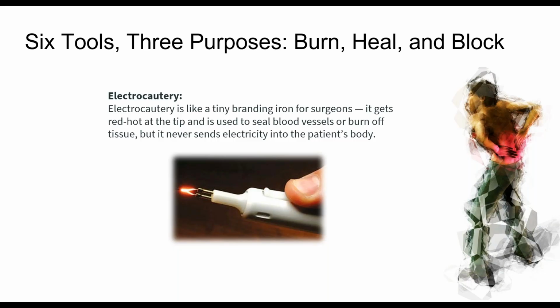Yet, if you look this up in Google, it'll say electrocautery and electrosurgery are the same thing. They are not. First of all, if you're using electrosurgery, you usually have a pad, or if you're using bipolar, you don't need it. But anyway, there is current going through the tissue. I don't care which one it was. With this one, there is no current at all going through the tissue. It is a tip that glows orange hot, and they can use this for small bleeders as well. They don't have to use electrosurgery.